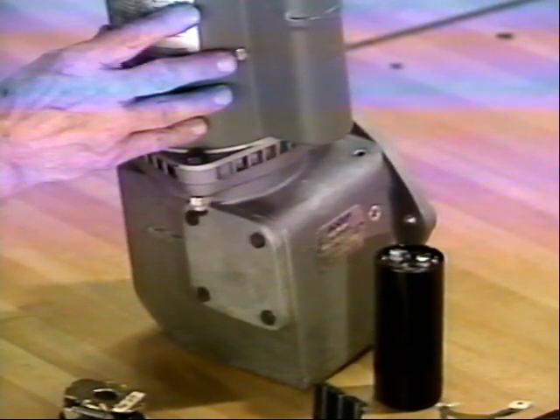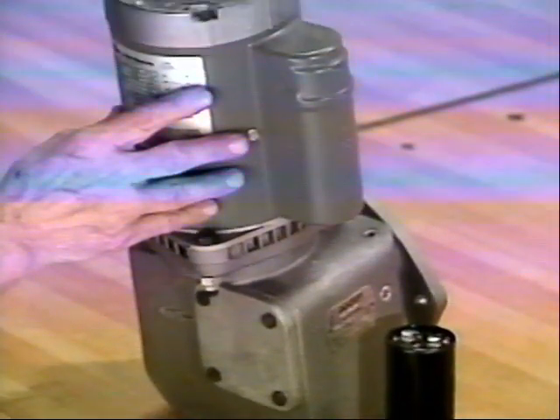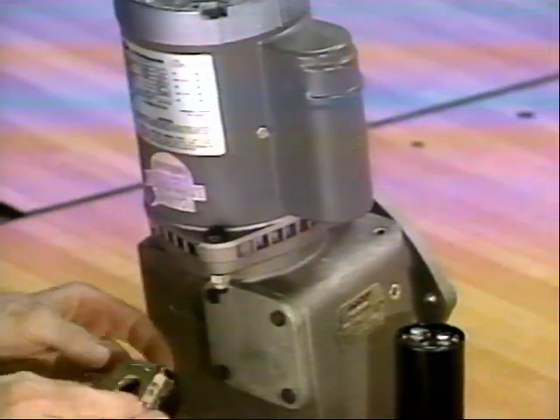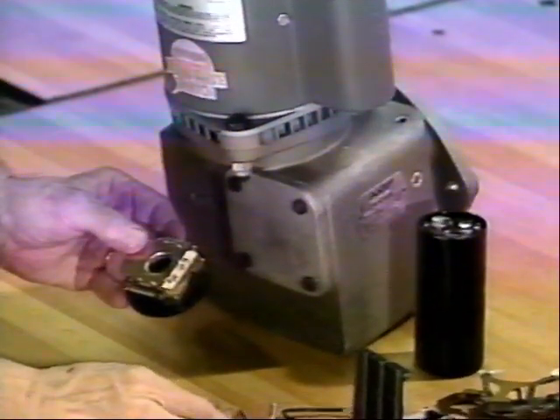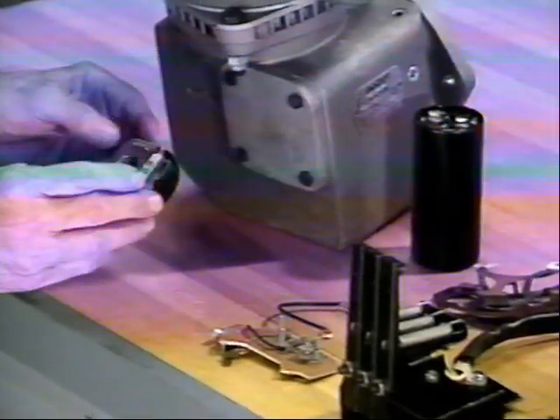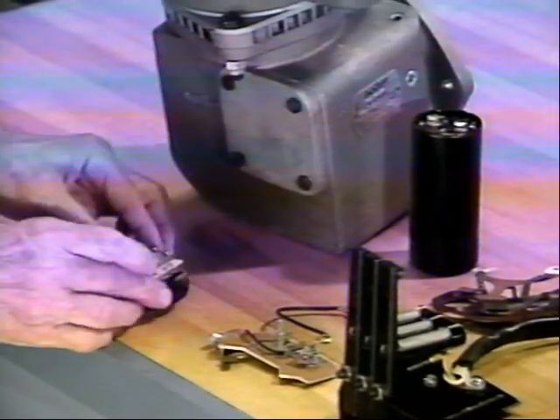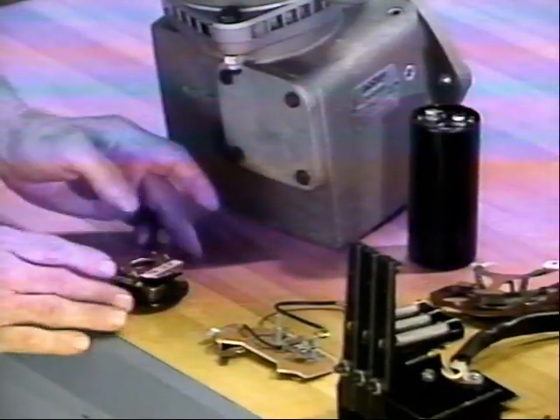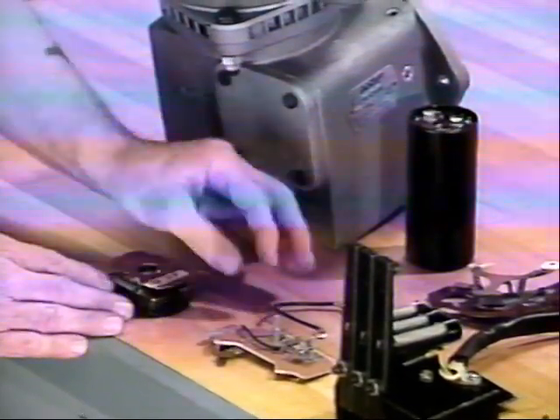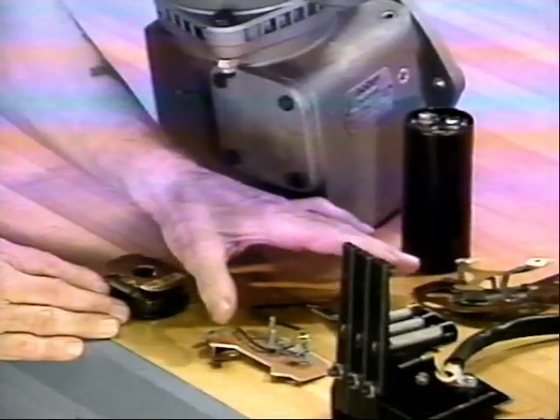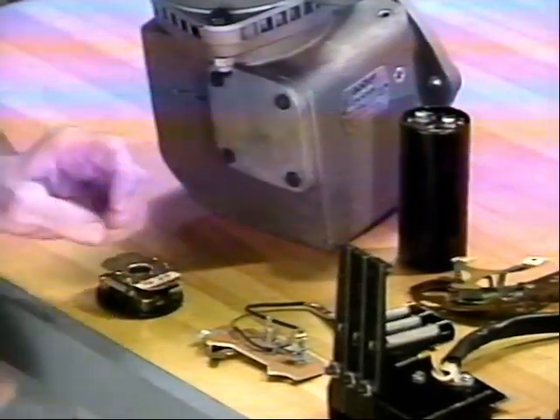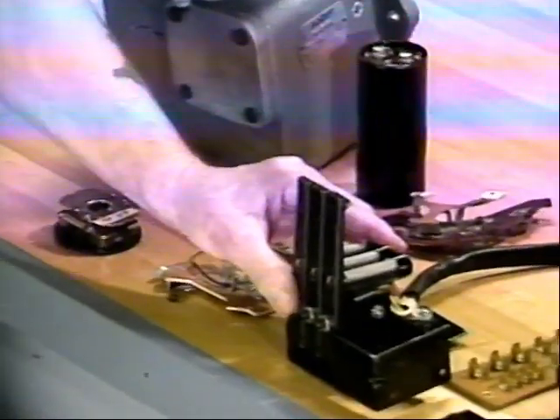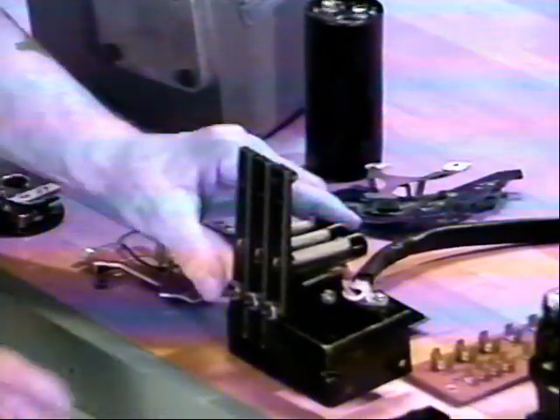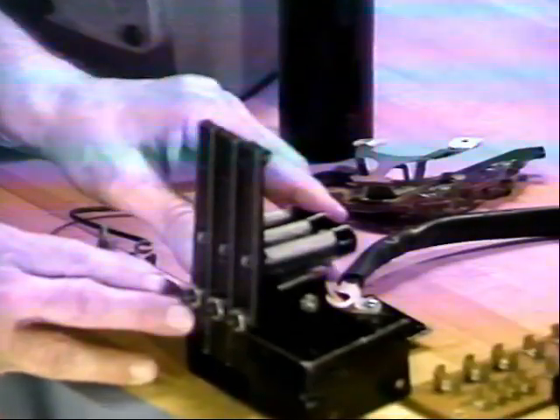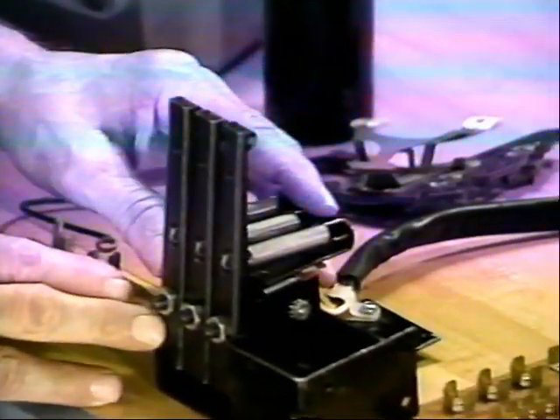Other motors, A.O. Smith, General Electric, or possibly National, used centrifugal mechanisms and centrifugal switches to put the start winding into and remove the start winding from the circuit in order to get the motors to run. So maintenance items would be the centrifugal mechanism as well as the various centrifugal switches. The motors are controlled in part by cam switches on the front of the machine. These are used in the run circuits and generally used to stop the motor in a particular position. So the switches would be part of our maintenance item.